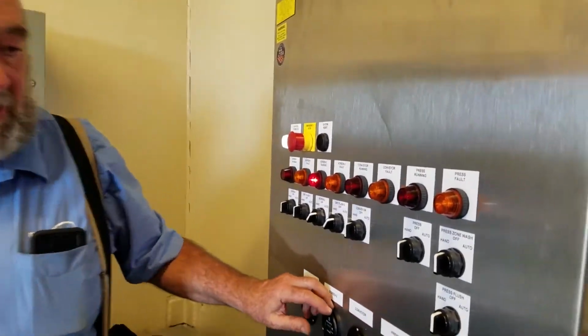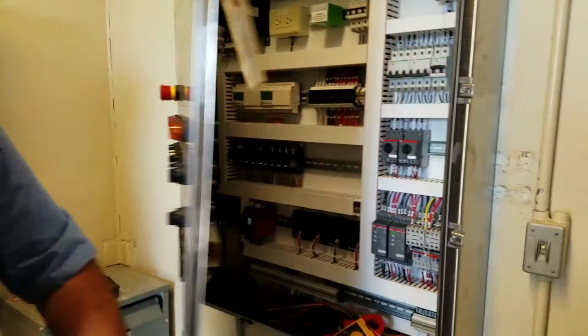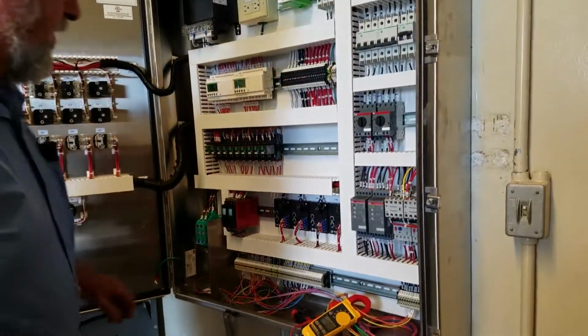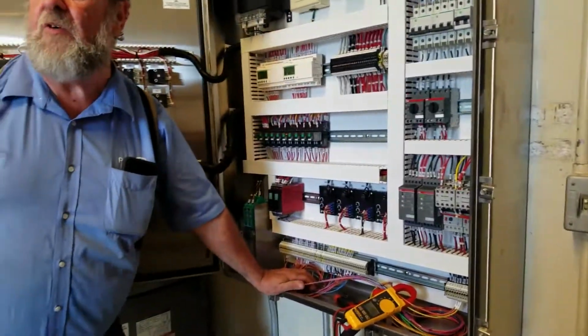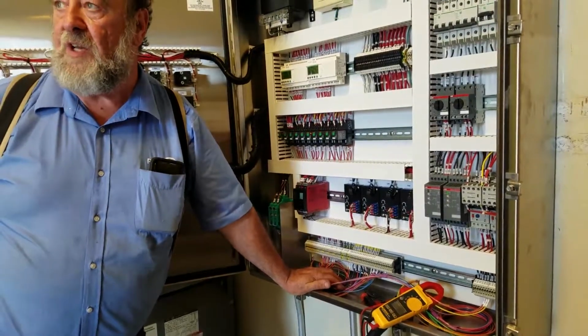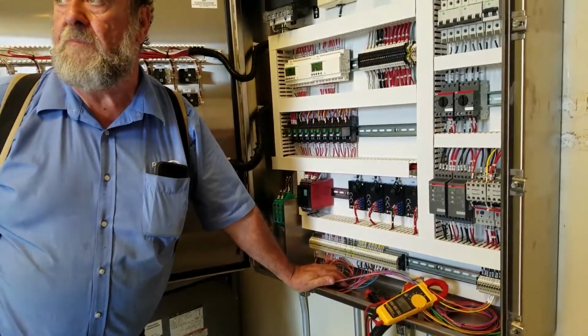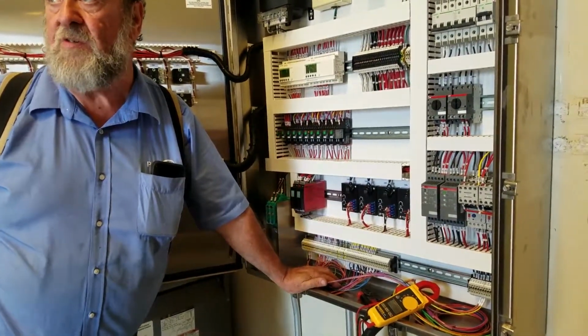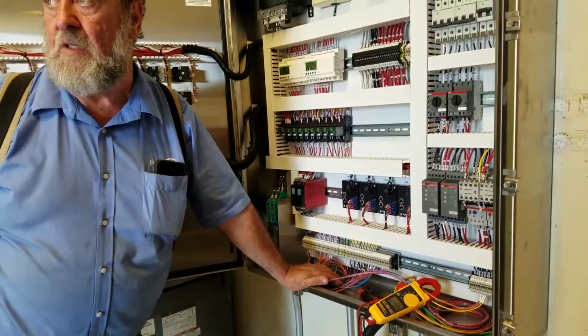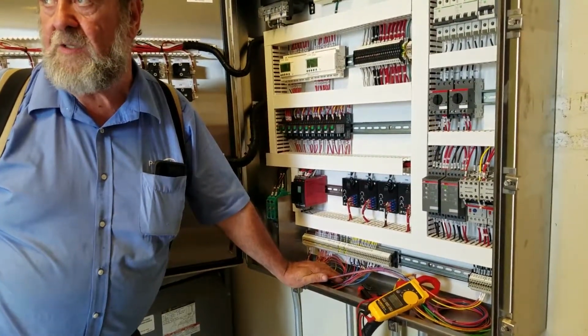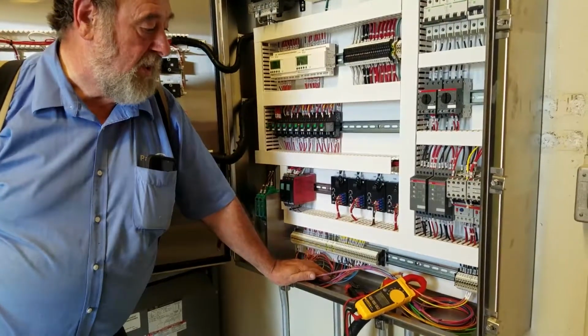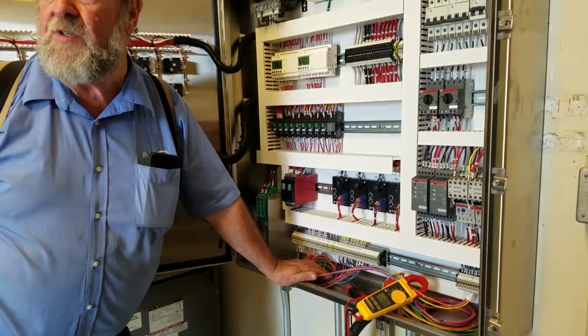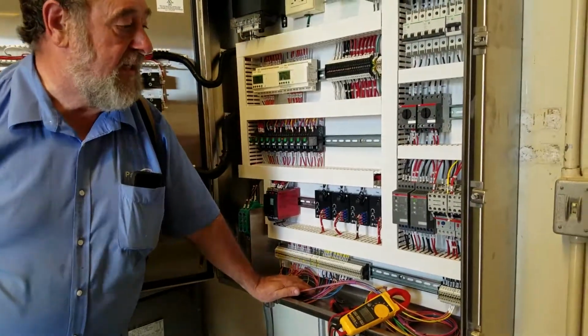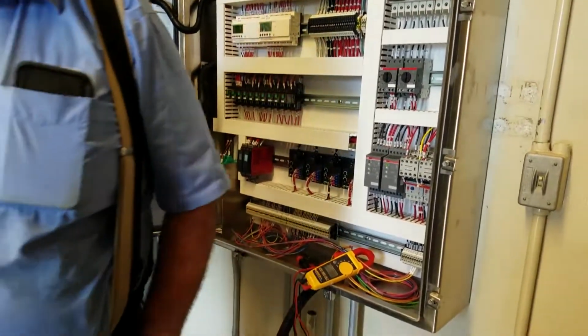And I guess what your system integrator is going to do, he's going to tap into the 4 to 20 milliamp signal coming out of that level controller and send it to your SCADA system so you can monitor your level in the channel from SCADA and also issue your high-level alarms to the SCADA rather than use dry contacts. That's what he wants to do. Have we got any other questions? All right. I guess we're going to go out there and work and take a look and go from there.